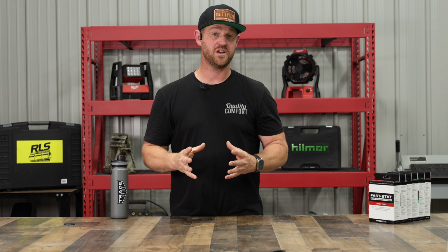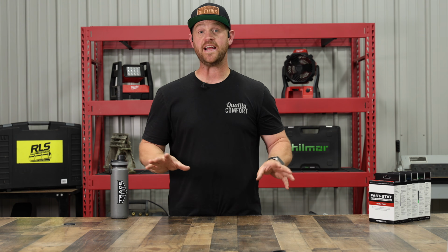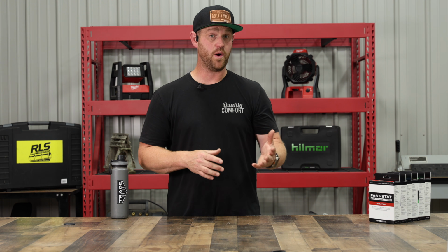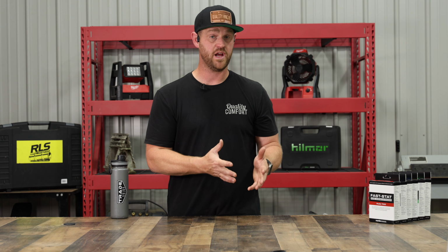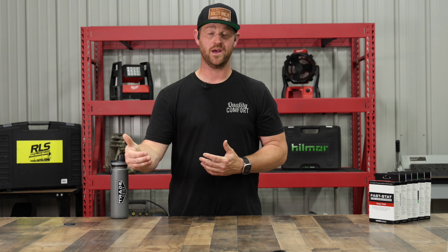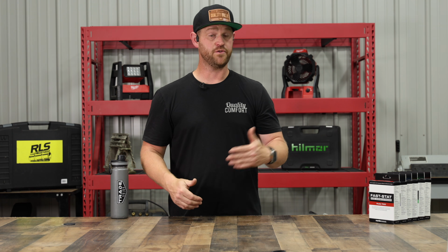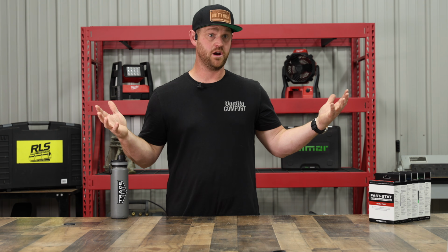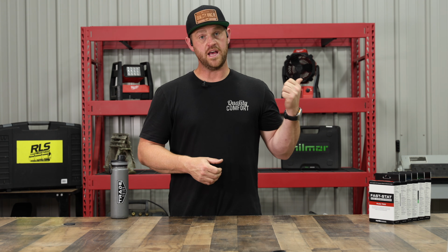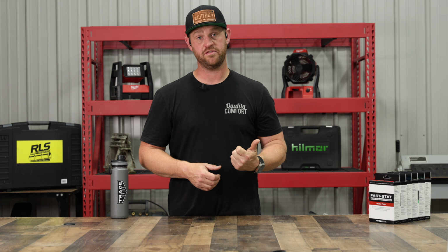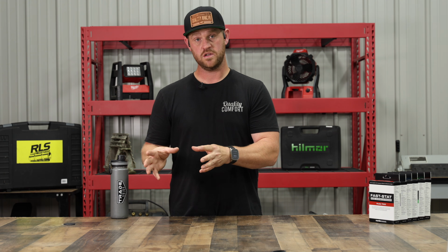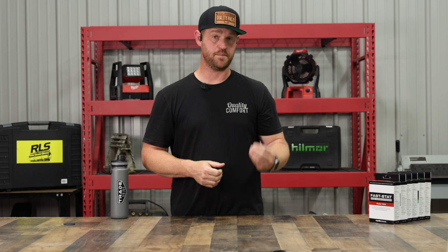One thing to know, an air conditioning system is not a dedicated dehumidifier. It doesn't control humidity in the house. It removes humidity as a byproduct, but if you don't have a dedicated dehumidifier and you only have an air conditioner, that's about the best that you're going to be able to do, is overshoot your set point to try to knock down that humidity. So if you're in a very humid climate, like here where I am in Tennessee, it's really good to have a dedicated dehumidifier that's ducted into your system, so that way it's controlling the humidity and then your air conditioner is controlling the temperature in the house.